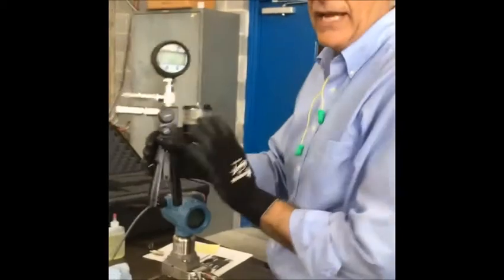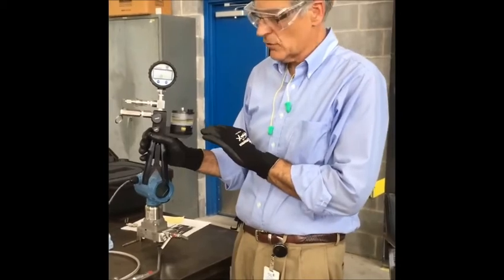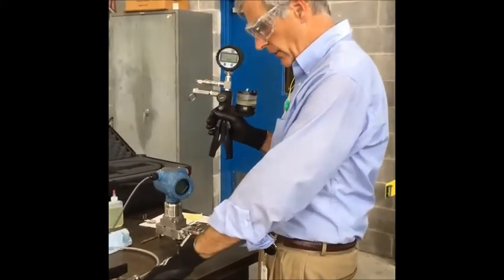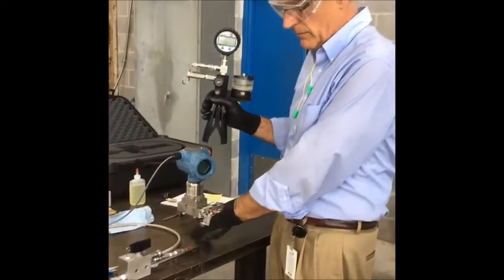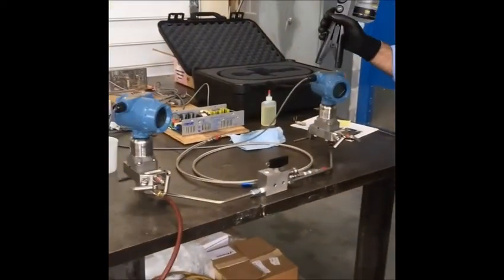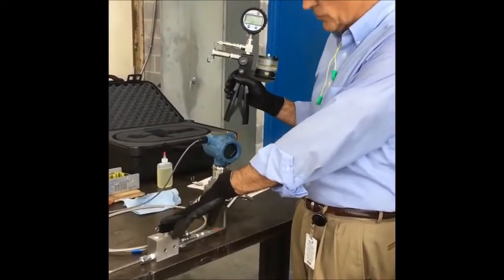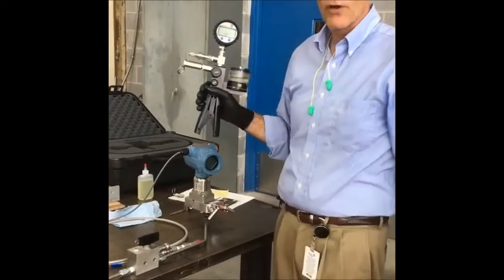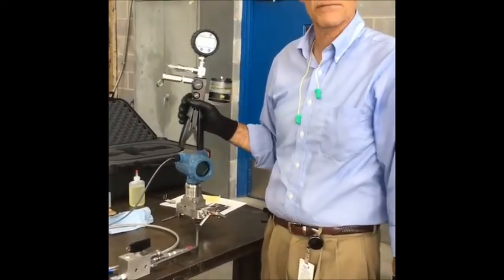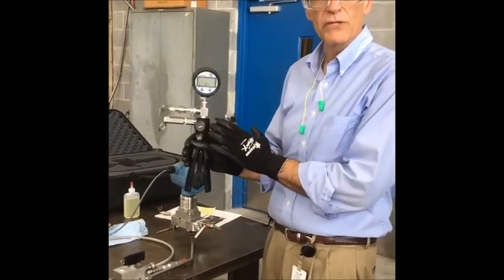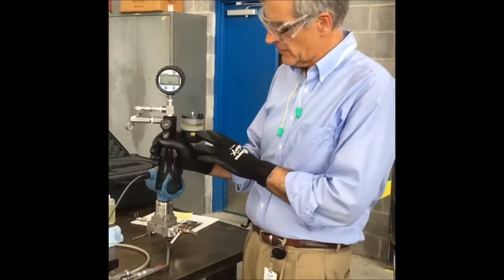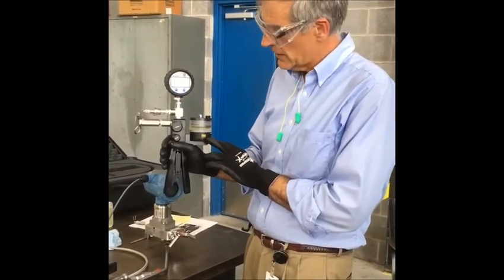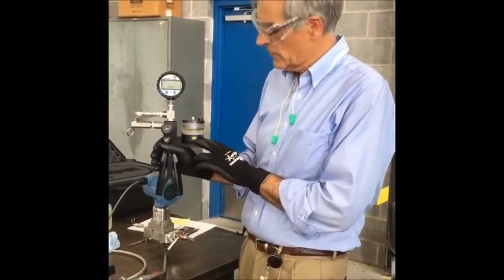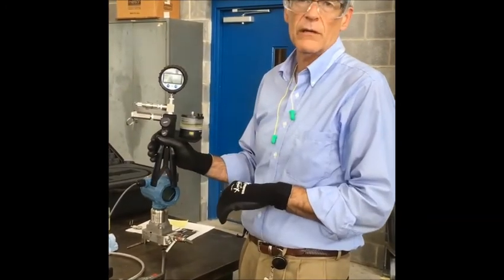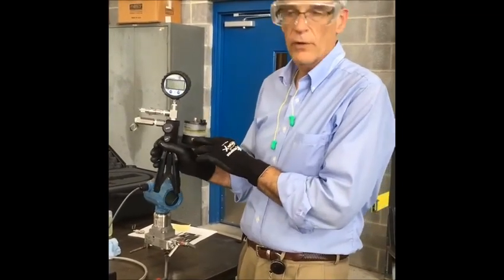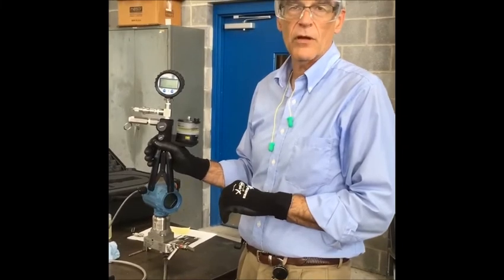We also don't recommend changing oil. One of the reasons we use refrigeration oil in the system is so that little bit of oil that I put in the high pressure line, when I pumped it up, will just run harmlessly back into the refrigeration system when I put this in run position. So it drains that little bit of high pressure oil out. There's no air introduced to the system, and there's no risk of leakage. But then we don't want to switch the oil that we use in the pump. There will be different O-rings in the pump depending upon the refrigerant that it's used on and the type of oil that's used. So generally we would say whatever your most common ammonia refrigeration oil is, use that in the reservoir and then don't switch it to something else. Use that same oil all the time.